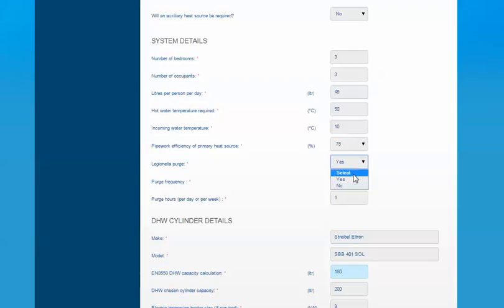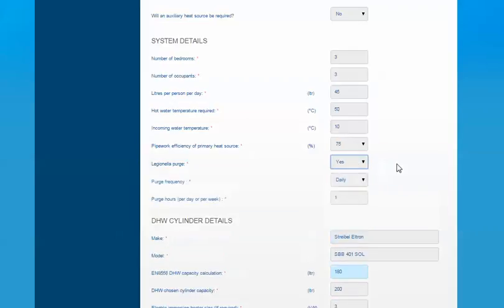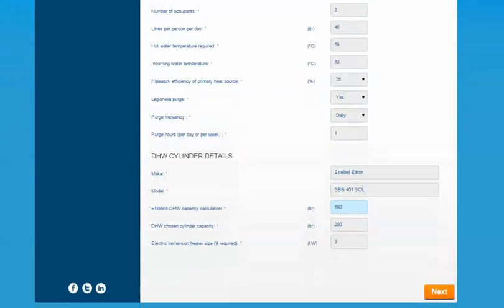You then have a question about Legionella purge. If you select no, then the final two questions will be removed. However, if there is a Legionella purge set up within the system, you'll then be asked about the frequency and purge hours. So for the frequency, you have an option for daily, weekly or monthly, and then the hours either per day or per week. A lot of manufacturers, certainly in the case of heat pumps, have built the Legionella cycle into the settings, and the software is just including this to allow a contribution towards the running costs to meet their extra requirement.